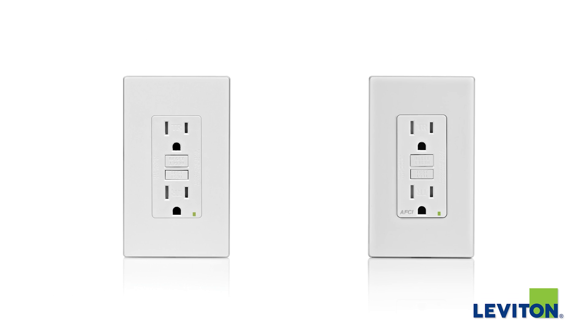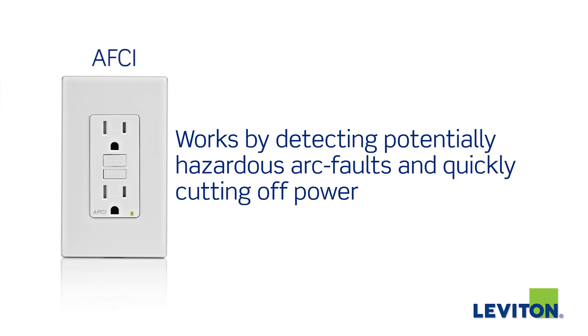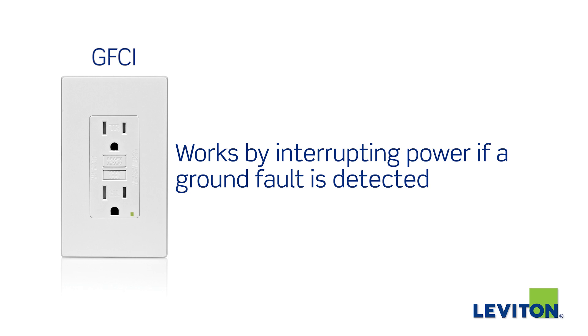You're probably familiar with GFCI outlets. Although they look similar, AFCI outlets function to protect branch circuit wiring from potentially dangerous arcing faults that could ignite a fire. GFCIs function to protect people from potentially harmful or deadly electrical shocks that could result from electrical leakage associated with a ground fault.